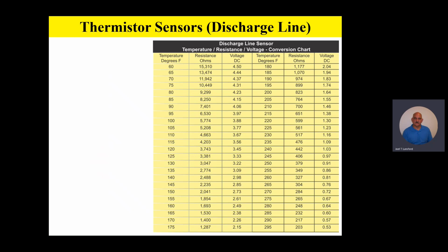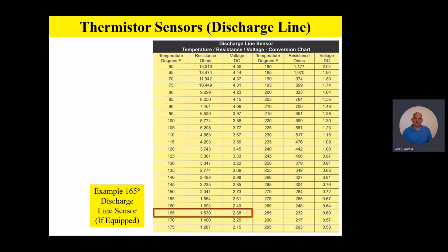So one final example, let's say, for instance, we do have a product, maybe it's one of our HL19 products, our higher end product, and it has a discharge line sensor. It may have a discharge line sensor on it. Well, these charts, they still work the same, team. Basically, what you're going to do is measure the temperature of that discharge line. You're going to clamp on your good high quality temperature probe, and you're going to measure the temperature of that discharge line if it's so equipped. And let's say that discharge line is 165 degrees Fahrenheit. If I unplug the sensor from the board and I go over and look at the resistance or the ohms column, I should read about 1,530 ohms with the sensor unplugged.